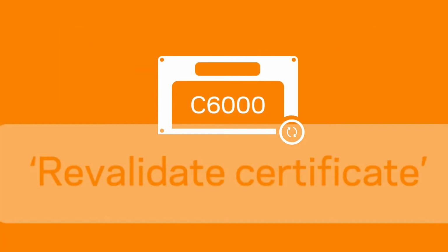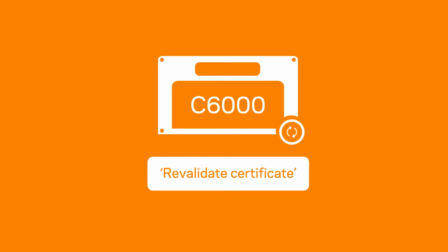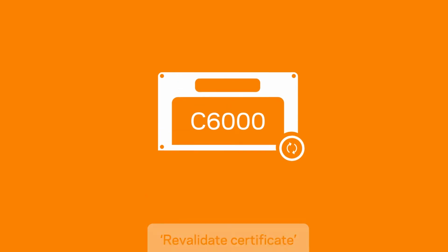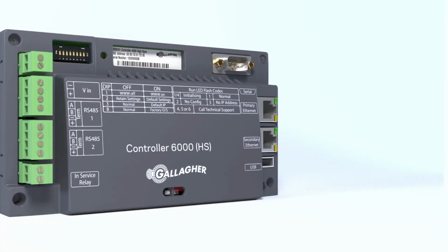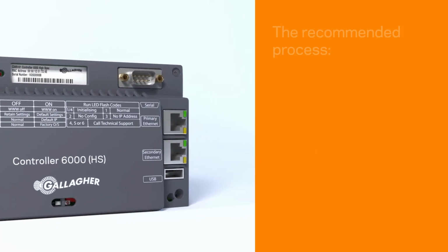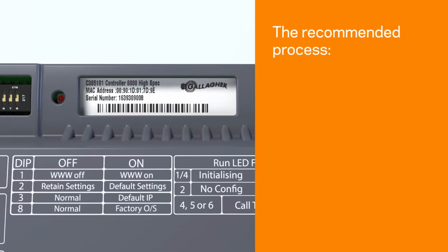In this case, a revalidate certificate override may be required to bring the controller online after the controller restarts with DIP switch 2 on. So let's go through the recommended process to upgrade the controller with factory firmware to the latest released version using the BootP method.